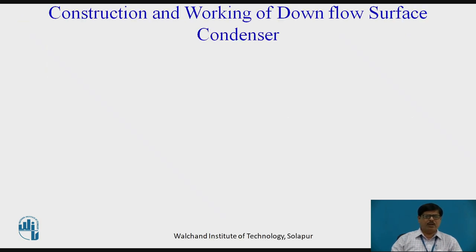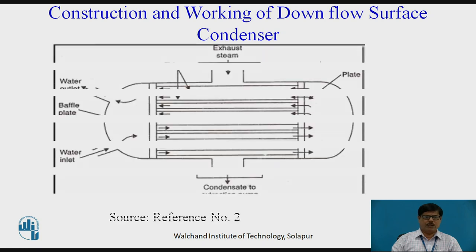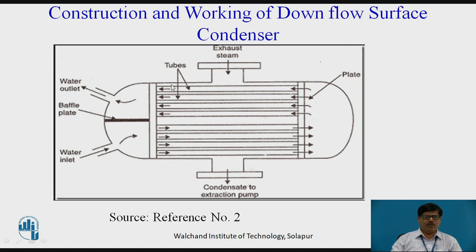Now we will discuss regarding the surface types of condenser. Firstly, we will discuss about the construction and working of downflow surface condenser. As we can see in this figure, the downflow type surface condenser has a cylindrical shell made up of cast iron, closed at each end with covers to form the water boxes. Inside this shell, tube plates are provided at each end between the condenser shell and end covers. These tube plates are provided with water tubes and at the center of this surface condenser, a baffle plate is provided to divide the water flow into two parts. The exhaust steam is admitted from the turbine from the top side and enters into the condenser shell.